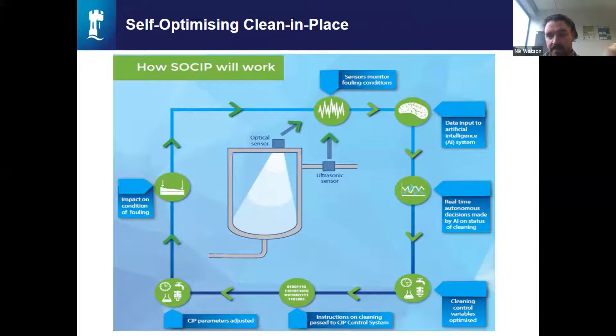So I've been working on the ultrasonic sensors on the pipe work, and my collaborator at Loughborough, he's been looking at ultraviolet sensors in the tanks, and we've been looking at, can we collect the data under different conditions, and develop these predictive analytics to detect fouling. And here for our intelligent sensor system, what we want to detect is the fouling in that piece of equipment, yes or no? So that's the requirement for our intelligent sensor system.